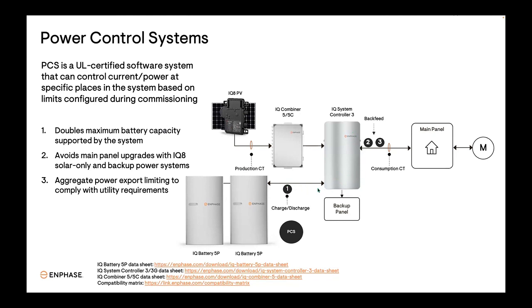So it's metering all of the electrical current flowing from the batteries into the system. And that allows us to limit the amount of current to whatever that overcurrent protection device is rated for in the controller 3. So typically that's going to be an 80 amp breaker, so up to 64 amps can be flowing through that circuit. So we can actually install more batteries than would normally be limited by that 64 amp maximum because of the fact that we can limit the current. Now, limiting the current is going to have a nominal impact on the system's capability of starting and running large loads. The continuous current is impacted, but peak output, which is of course important for starting appliances, is not impacted by PCS. So that system's still going to have the same capability of starting big appliances with its multiple batteries.